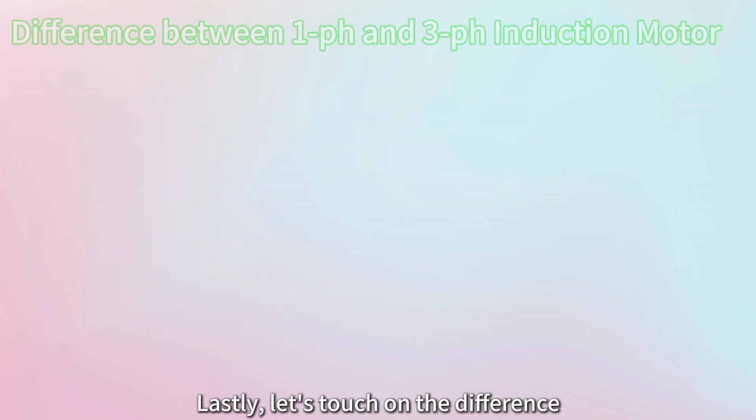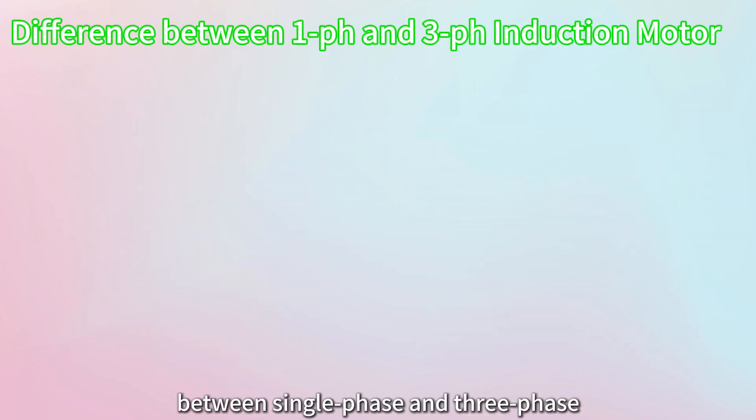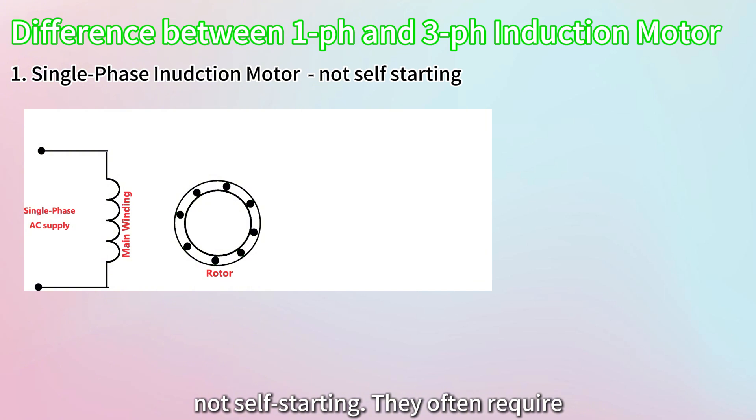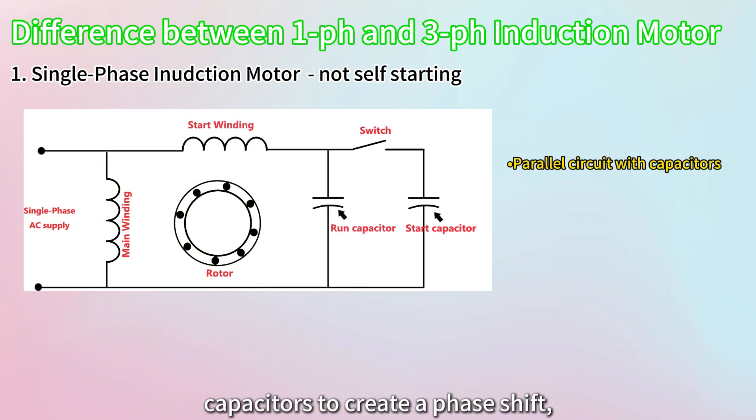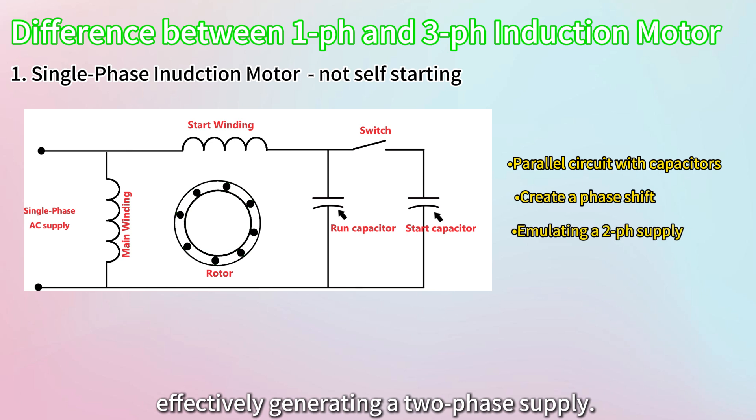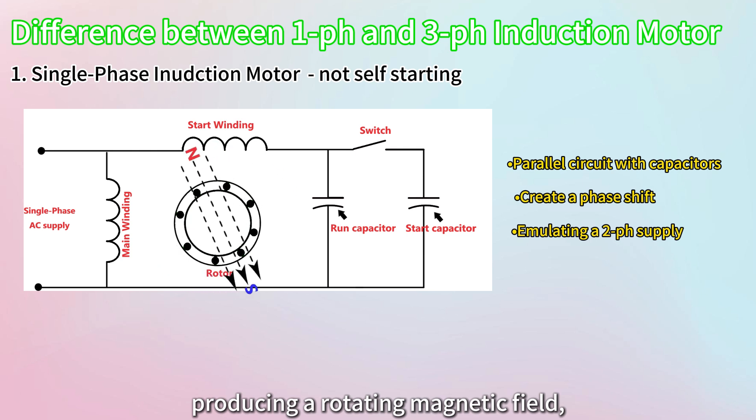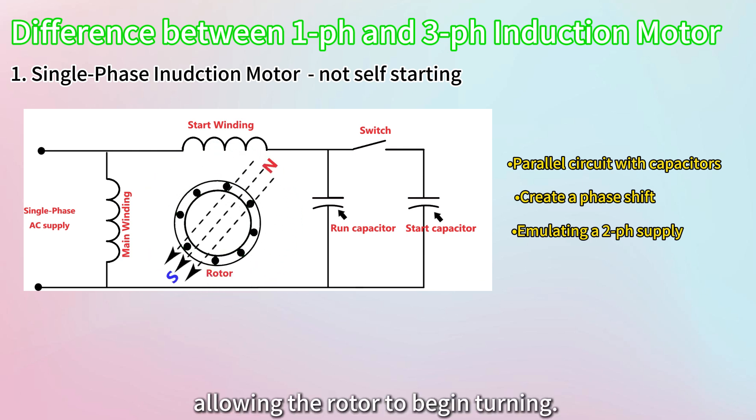Lastly, let's touch on the difference between single-phase and three-phase induction motors. One key distinction is that single-phase induction motors are not self-starting. They often require capacitors to create a phase shift, effectively generating a two-phase supply. This phase shift is crucial for producing a rotating magnetic field, allowing the rotor to begin turning.